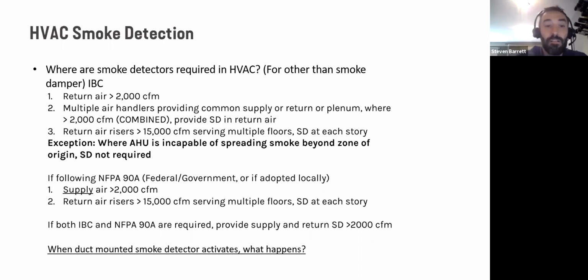Now, if you've worked on federal projects, government projects, NFPA 90A, it also can be adopted locally, but that's kind of the opposite. They require the smoke detector on the supply side. Still over 2000 CFM, so it's the same cutoff. And then they also have the same requirement for return air risers greater than 15,000 CFM to provide the smoke detector at each story on the return side. So you may have a project that has both IBC and NFPA 90A, in which case you would provide smoke detectors on both the return and supply side for units exceeding 2000 CFM.